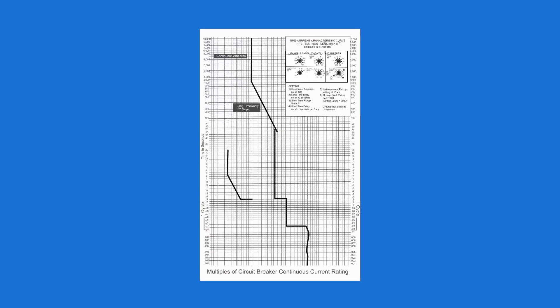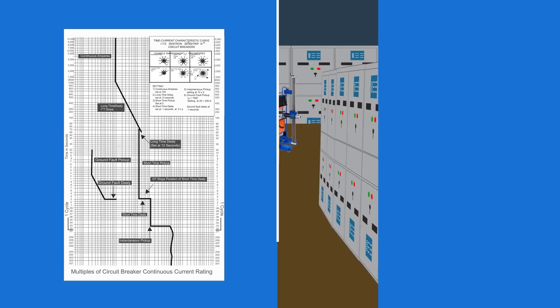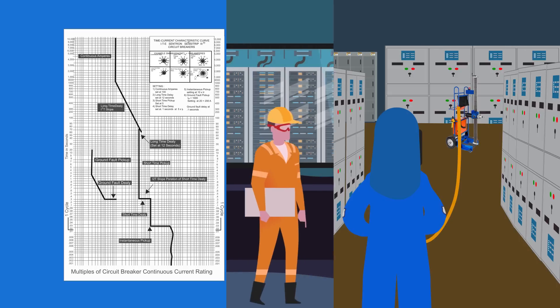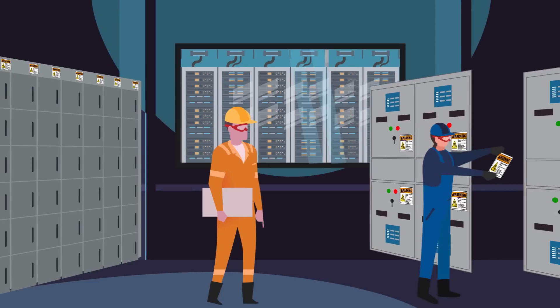Specify required PPE levels based on the existing electrical safety program in place for the facility. Identify areas where incident energy levels can be improved and provide settings changes and/or mitigation steps. Settings changes should be made while ensuring proper protective coordination.